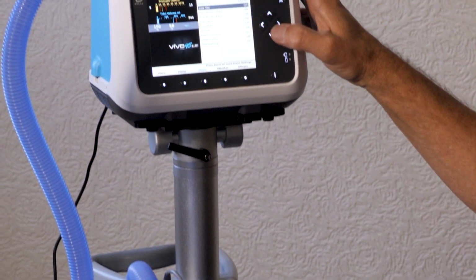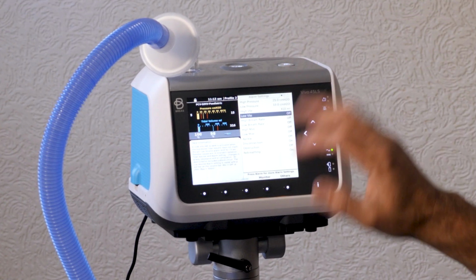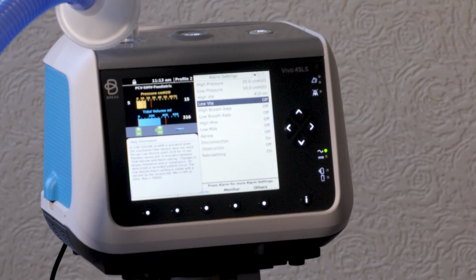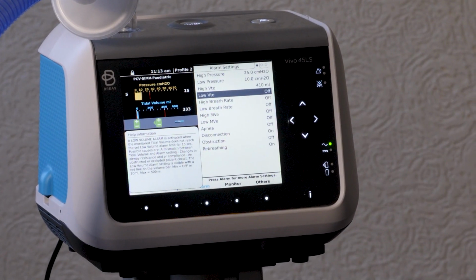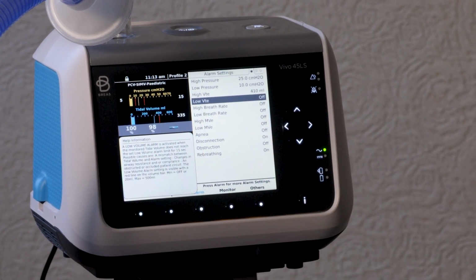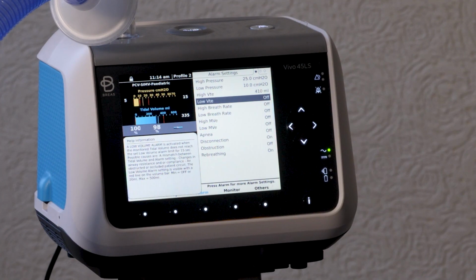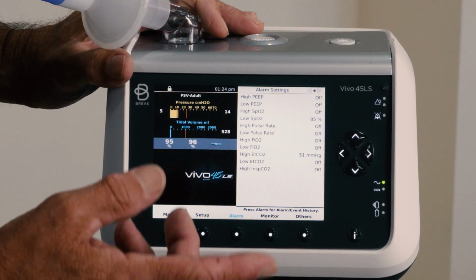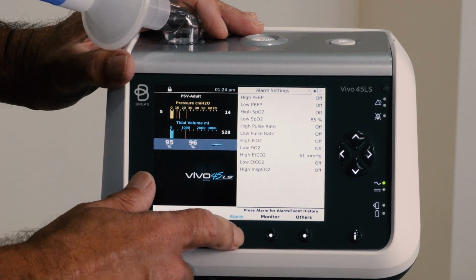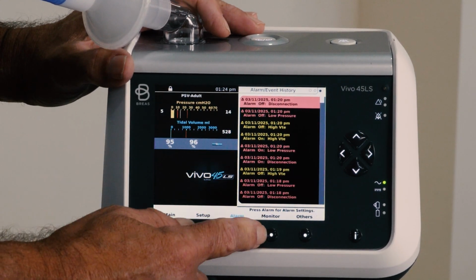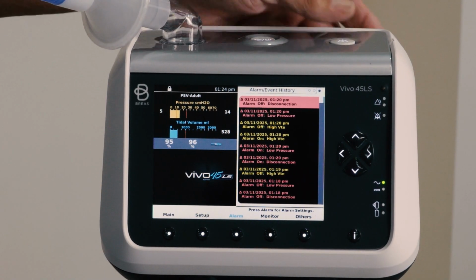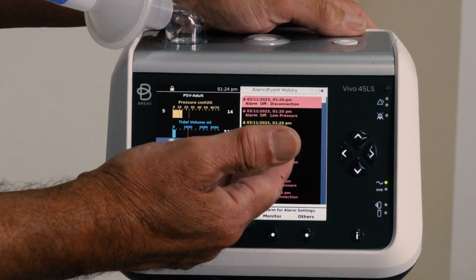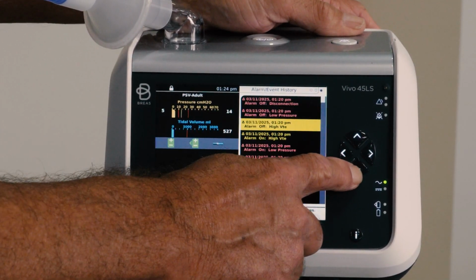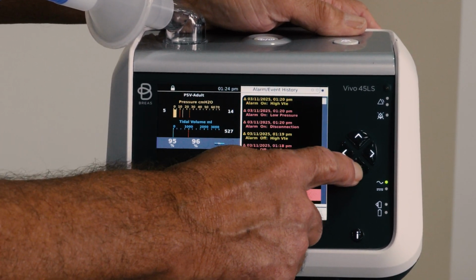Learn your alarms, highlight them, hit the I button, and become very familiar with what the alarm means, the possible cause, and how to troubleshoot that particular alarm. So if I hit the alarm button one more time, now I'm going to get into the history of all my alarms. And as you can see here, you have your red, you have your yellow, and if I continue on down, you're going to see some white.